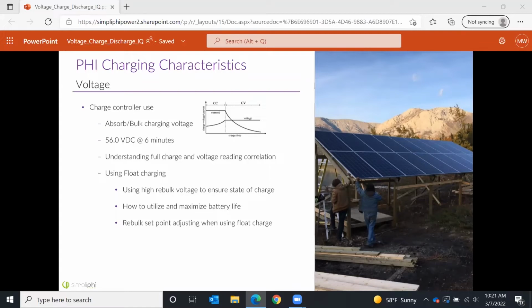One thing to note is understanding the full charge and voltage reading correlation - when are your batteries actually full? I notice a lot of people finish the absorb charge stage after 6 minutes at 56 volts, and their batteries will still be taking in a significant amount of current during the float stage afterwards at 54 volts. So keep in mind, the best way to know when your batteries are completely full is when the charge current has tapered off to 2% of the amp hour capacity. That's how to entirely top them off. You don't want to go all the way until they're accepting zero current - that's just going to overcharge them and not let them last as long.